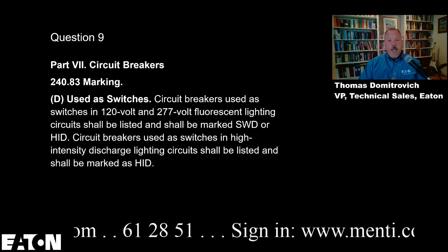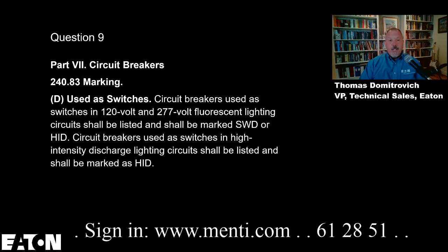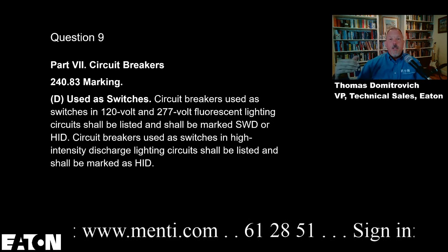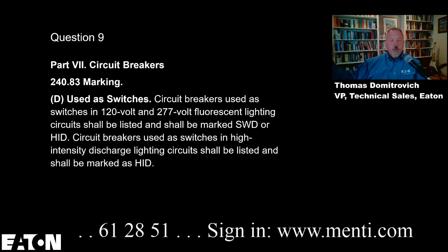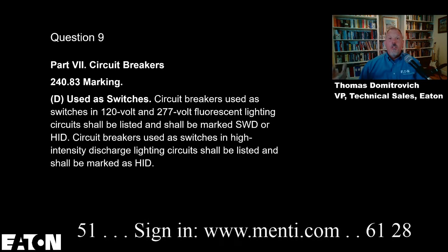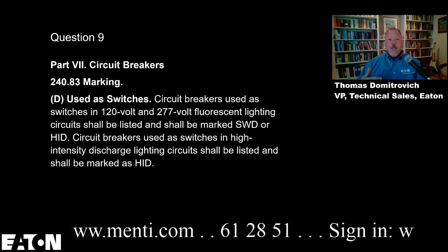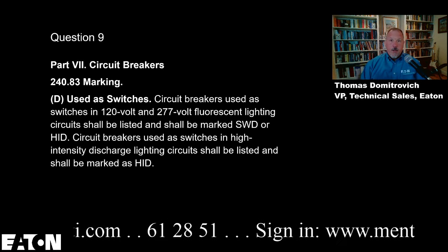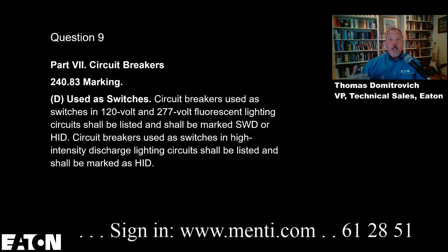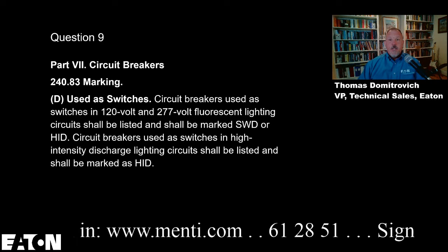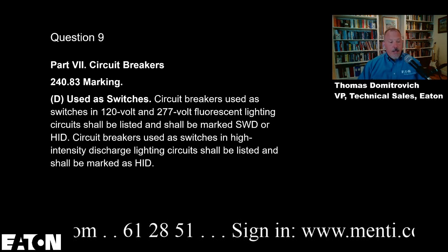So a breaker that's marked HID can handle the switching, from a durability and endurance perspective, for HID and for fluorescents, and the power factor is no worse for HID, but you can't use the SWD on an HID circuit because you need the HID breakers, probably because of the power factor that we're testing those at.